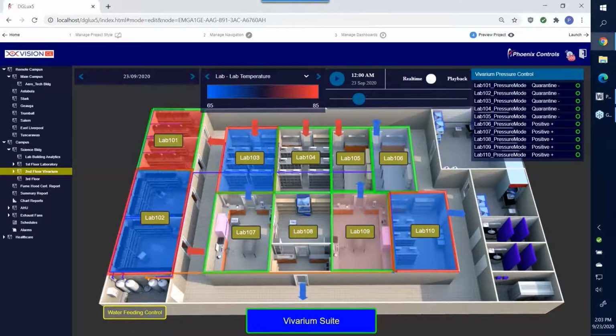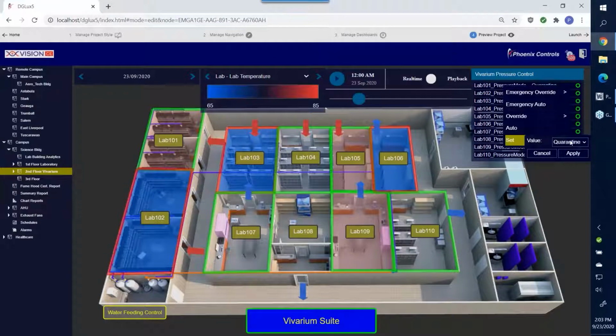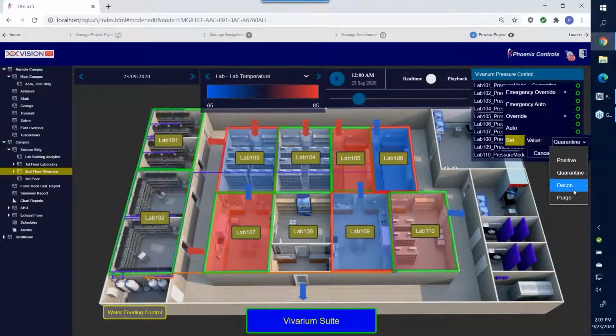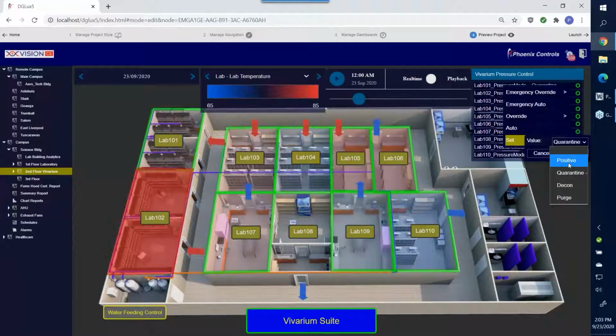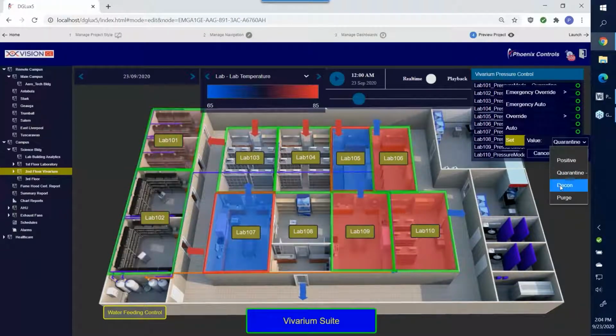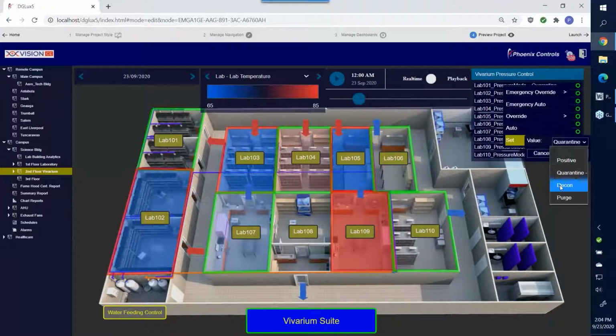If we go into Lab 101 and push on that, then go to set, we see several options: we can make the space positive, switching the relationship to the supply and exhaust valve; quarantine, changing the relationship so there's more exhaust versus supply; decon mode, where with 100% shutoff valves we can seal the space for VHP cleaning and other means of isolation; and ultimately a purge.